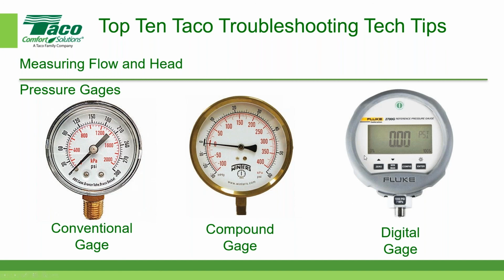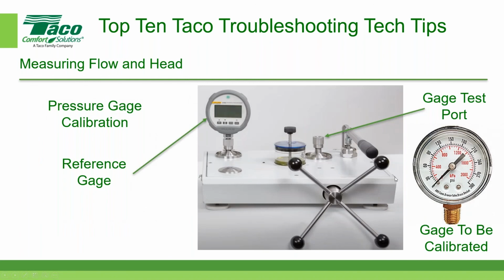And some of the newer gauges are the digital gauges. They're really good. They can read positive and negative values, and they can also read in PSI and in feet. So it's all kinds of good stuff. How do you calibrate a gauge? Well, I'm not going to go into a lot of detail, but this is an instrument for calibrating the gauge. This is the reference gauge over here on the left. You screw the gauge into the gauge port, you pump up the pressure, and then you can fine tune the pressure with this rotating wheel here.